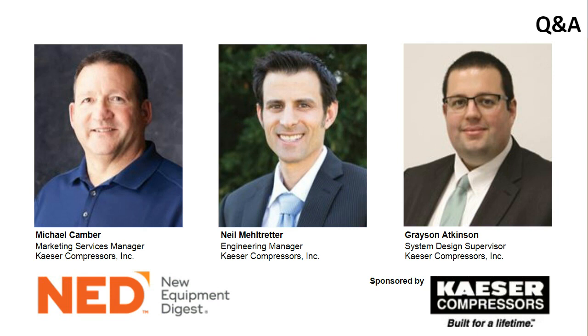Heatless dryer, desiccant dryer, there's also heated dryers, heated desiccant dryers. Both of those types, heatless and heated desiccant dryers, have options in regard to purge savers, and I would refer to them as dew point control as well. And these are going to be great because you're going to have a lot less energy consumption, specifically on the heated dryers and, let's say, a blower purge desiccant dryer. So if I were to buy a blower purge or a heated desiccant dryer for my facility, I would have to have dew point control.